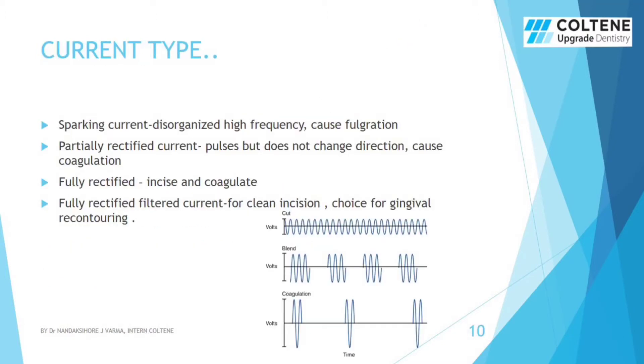The different effect is caused by a change in the current type. A fulguration is caused by a sparking current with disorganized high frequency. A partially rectified current pulses but does not change direction, causing coagulation. A fully rectified current causes incision and coagulation. A fully rectified filtered current is used for clean incision, which is the choice for gingival recontouring.